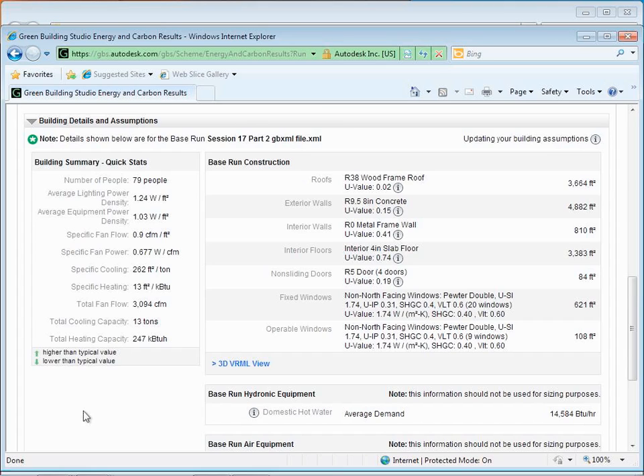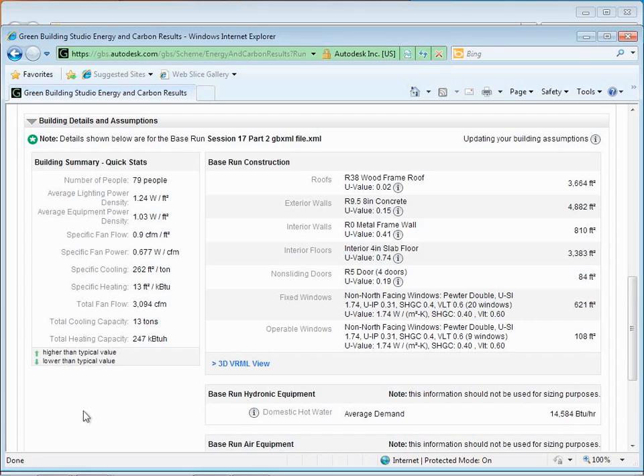Here in the windows, we have a little bit of information about those windows and what the U-values are. Looks like they're double-insulated or double-glazed windows that have a certain shading coefficient. But there's information here about basically how things are designed right now. So if I was looking at this and looking at things, I'm looking at the roof and thinking there may not be very much to improve on the roof because R-38 is actually a pretty well-insulated roof. The walls, there was some room to improve on. We could also start playing around with the windows. But the idea is to really go through and for each of the different variables, tweak them a little bit and see if you have much of an impact so you can figure out really which are the ones that make the biggest difference.